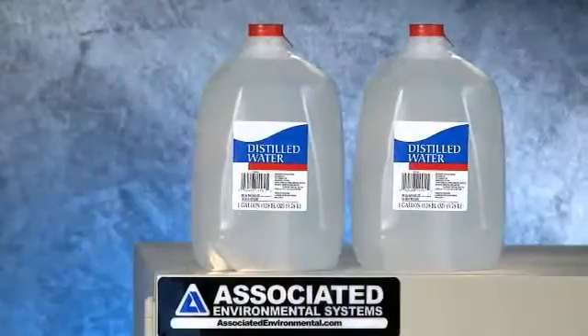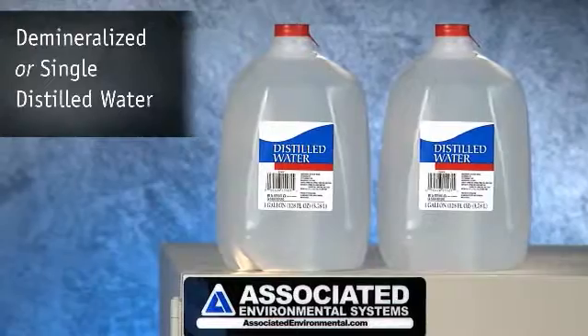Before we get into the differences between the water demineralizer system and the water recycling system, let's discuss the water required by all AES humidity chambers. Humidity chambers require water to produce humidity. Using the correct water is very important. AES humidity chambers are designed to operate using demineralized or single distilled water.